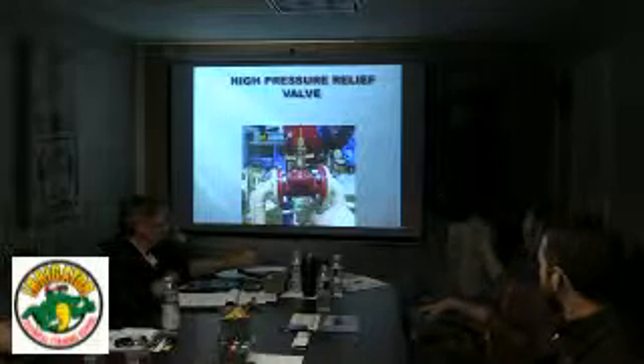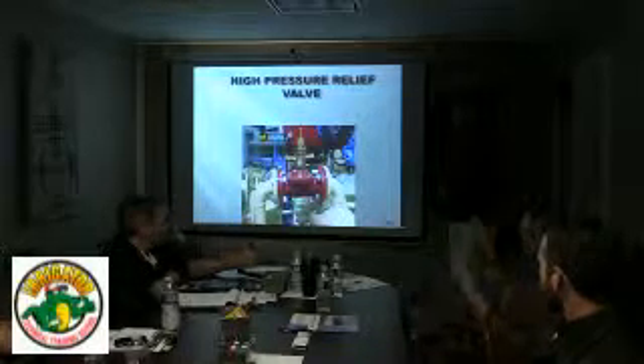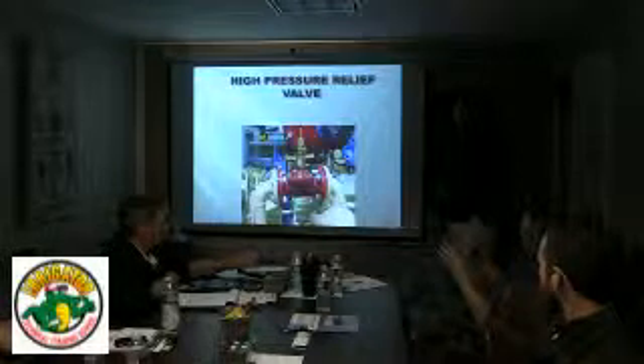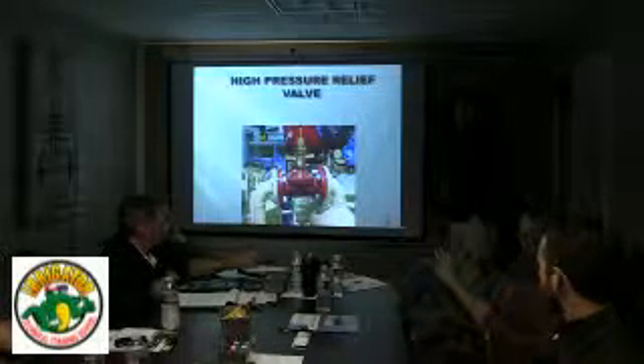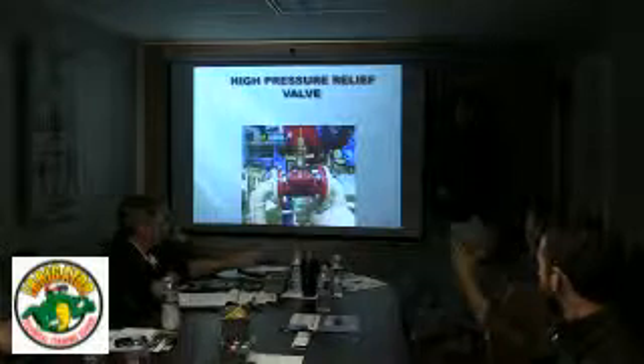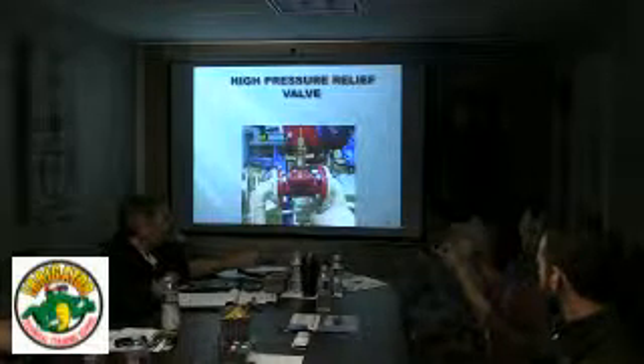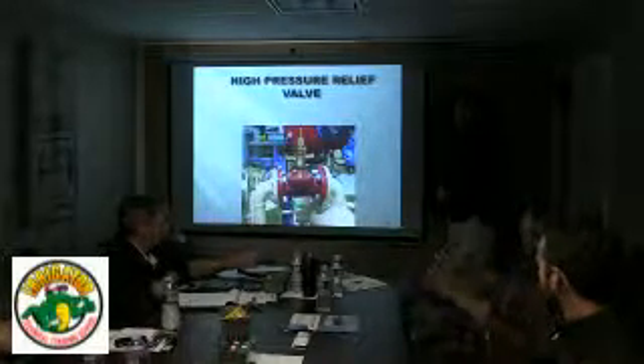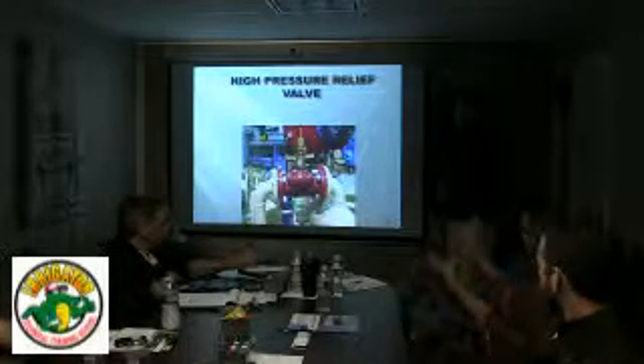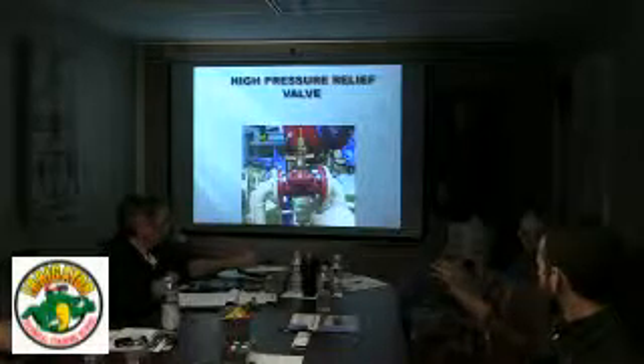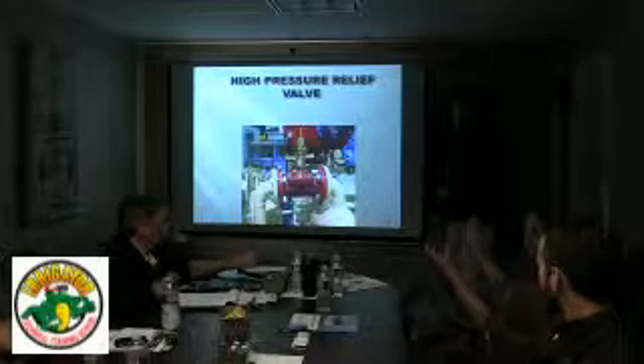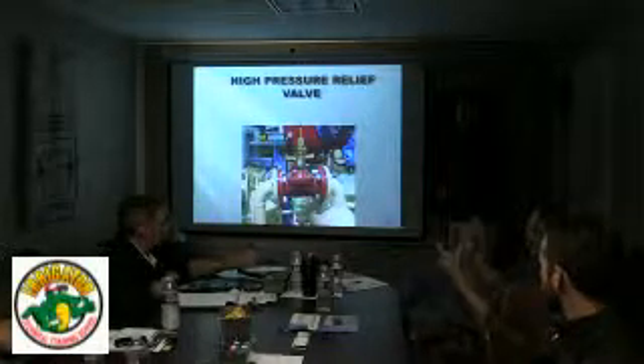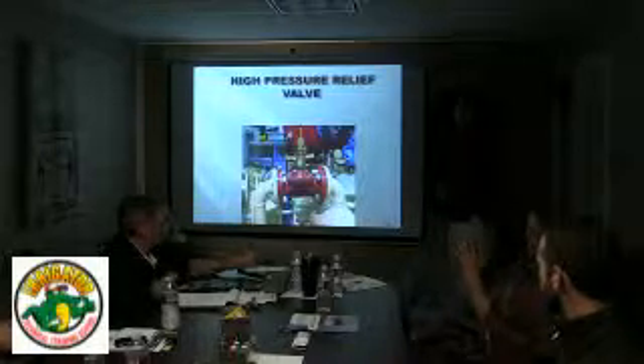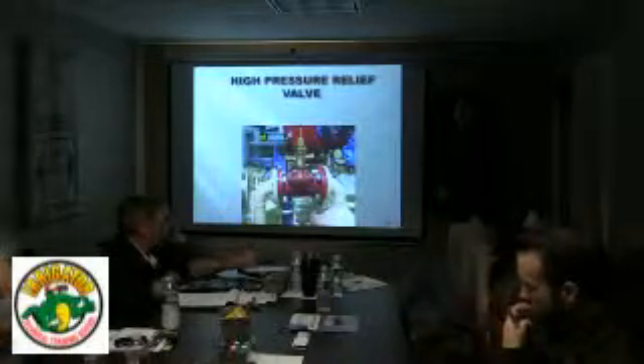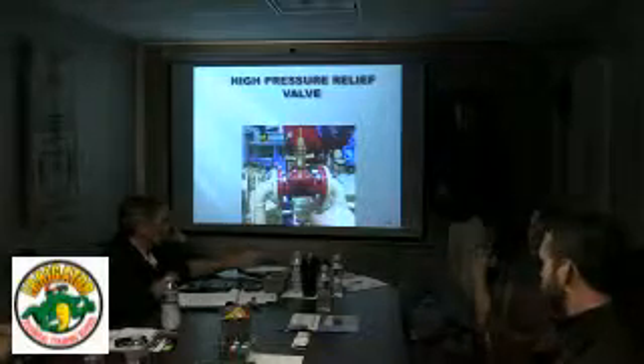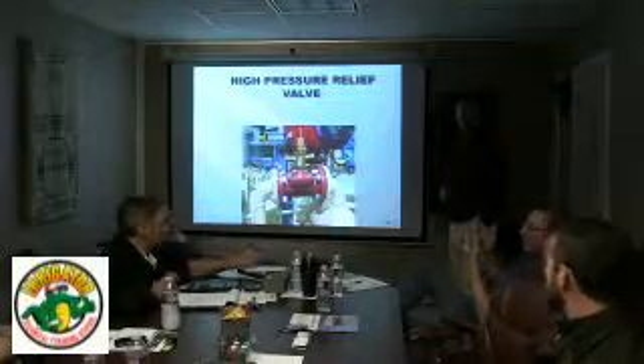So if you look at the materials, you'll actually see them wear out. They'll have a little ring, or even still the actual kit will have little nice fresh yellow squiggly lines. About 12 months, if you were to take it apart a year later, you can just look at it to clean it. You would see those squiggly lines start wearing out, and that's when they recommend to change it out. The rubber will still be pliable, but what you're looking for are blisters and maybe cracks. You want to prevent that from happening. So again, that's what I call preventive maintenance.